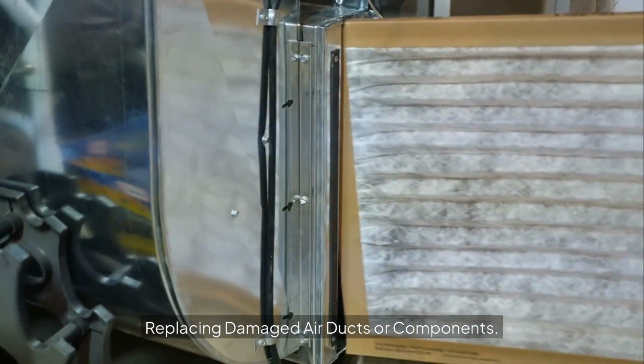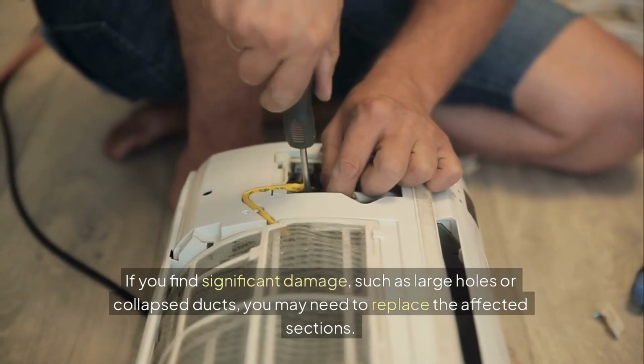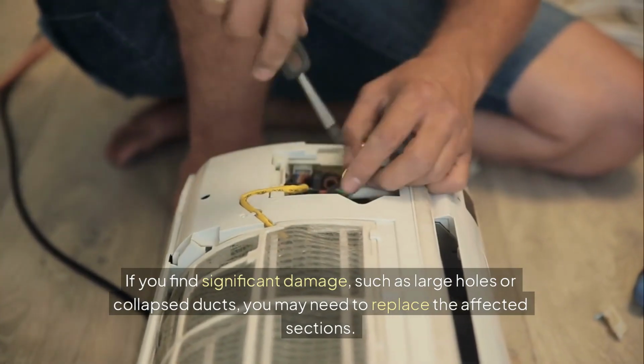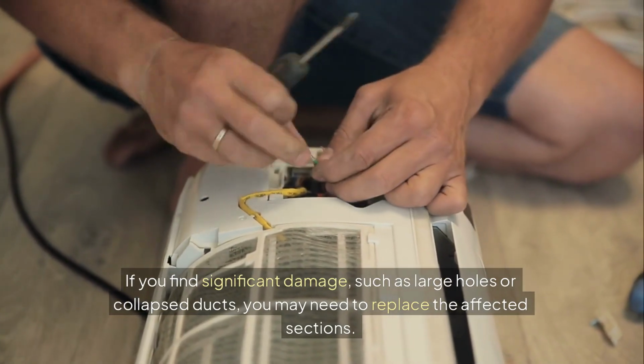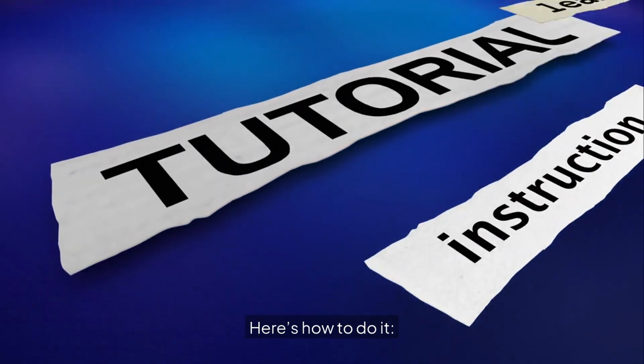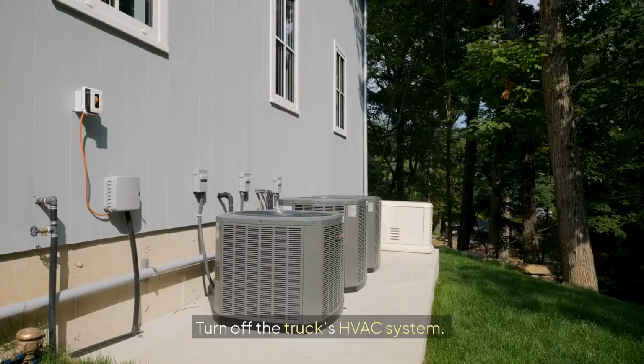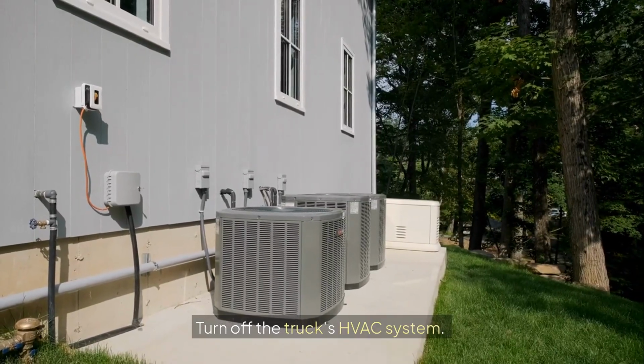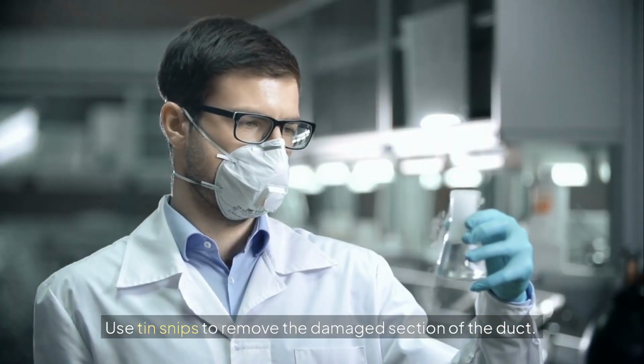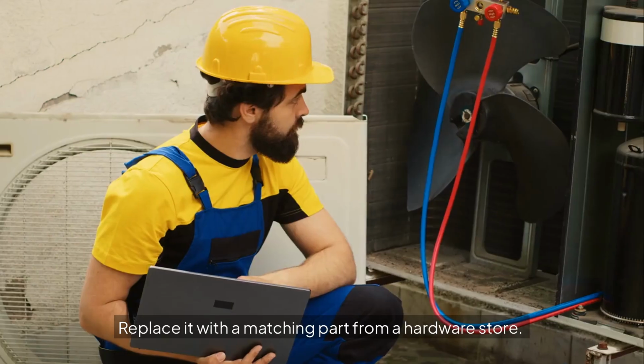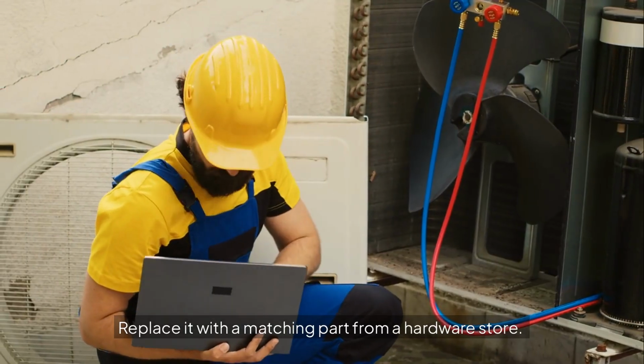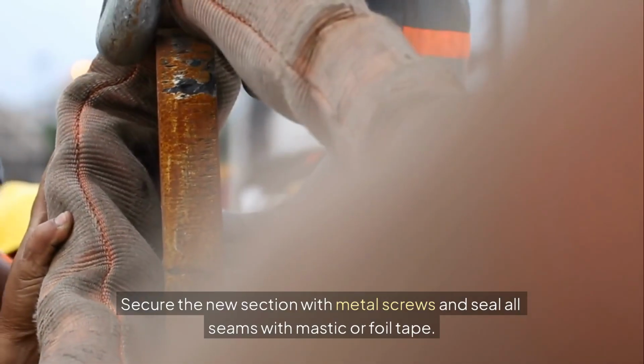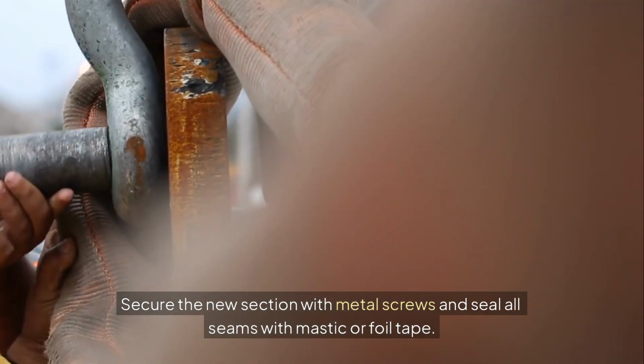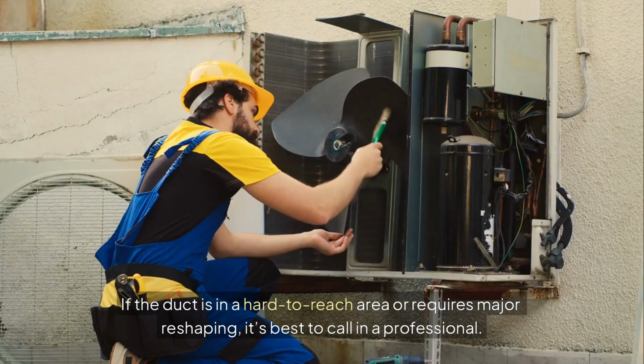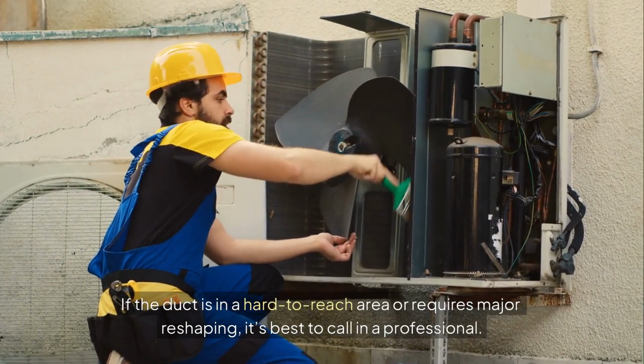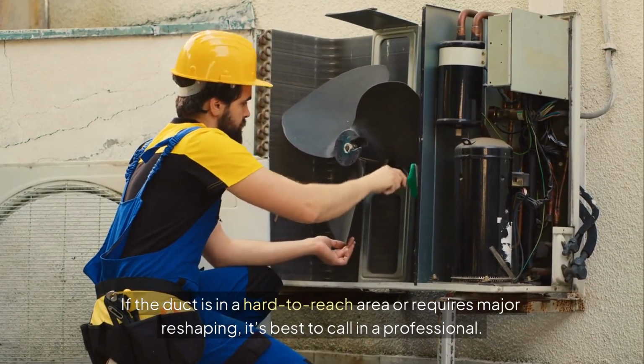Replacing damaged air ducts or components. If you find significant damage, such as large holes or collapsed ducts, you may need to replace the affected sections. Here's how to do it. Turn off the truck's HVAC system. Use tin snips to remove the damaged section of the duct. Replace it with a matching part from a hardware store. Secure the new section with metal screws and seal all seams with mastic or foil tape. If the duct is in a hard-to-reach area or requires major reshaping, it's best to call in a professional.